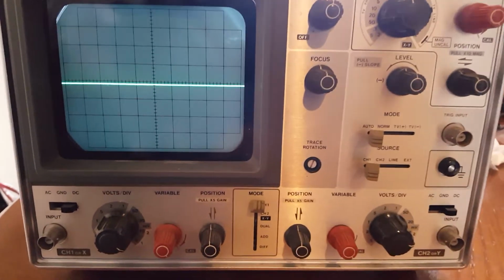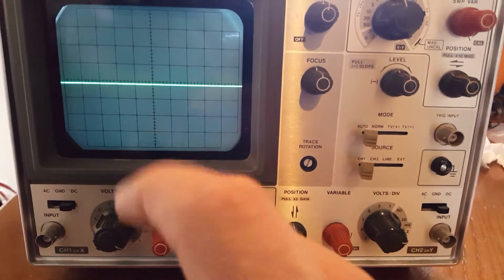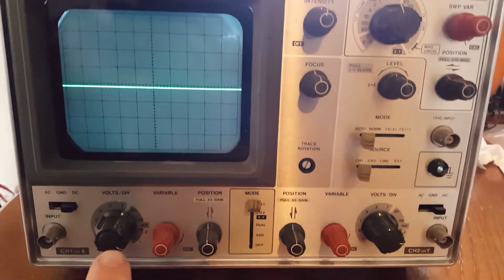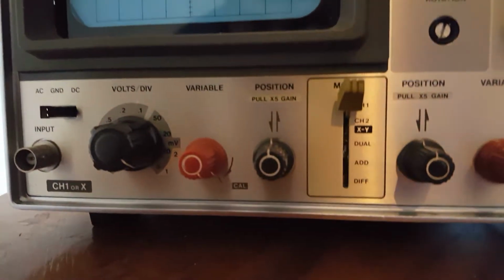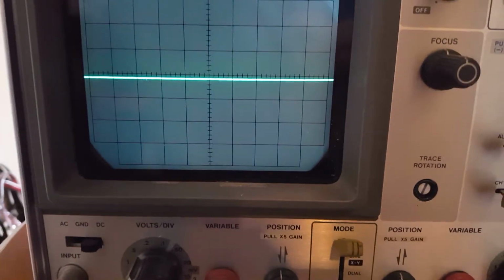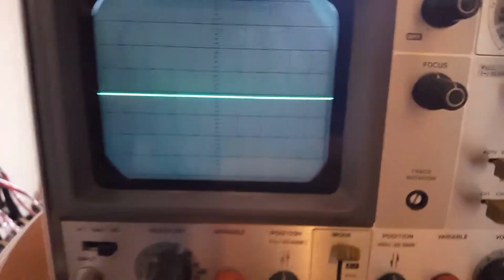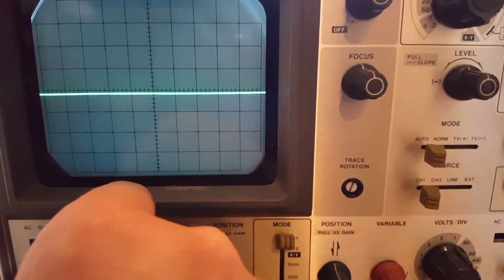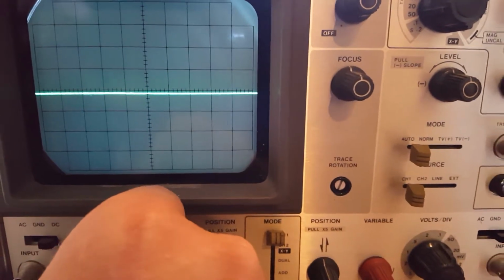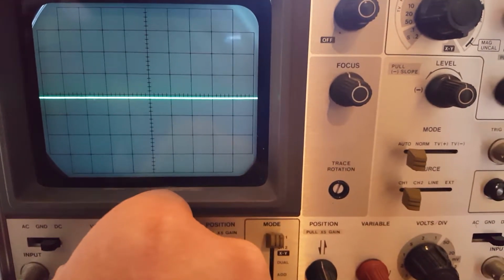To determine if your volts per division is balanced correctly, when you switch from 5 millivolts, which you can see it's currently on, to 10 millivolts, there should only be a tenth of a division movement in the trace. If I flip that, you can see there's only about a tenth of a division movement.